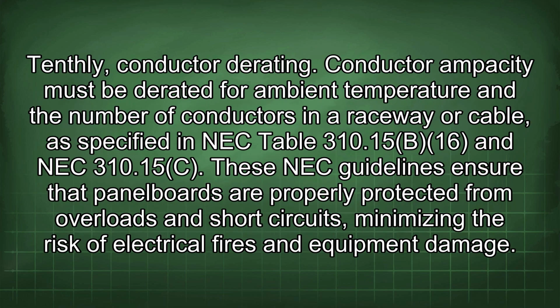Tenthly, conductor derating. Conductor ampacity must be derated for ambient temperature and the number of conductors in a raceway or cable, as specified in NEC Table 310.15(B)(16) and NEC 310.15(C). These NEC guidelines ensure that panel boards are properly protected from overloads and short circuits, minimizing the risk of electrical fires and equipment damage.